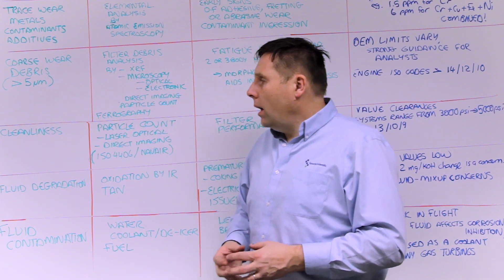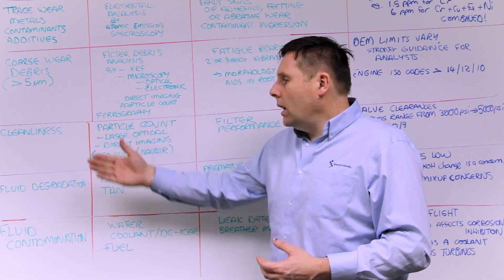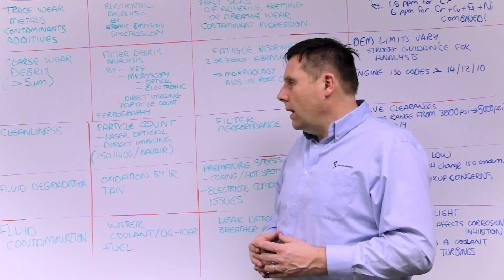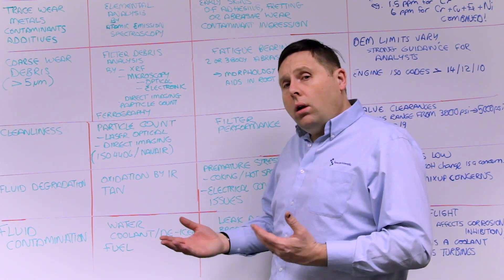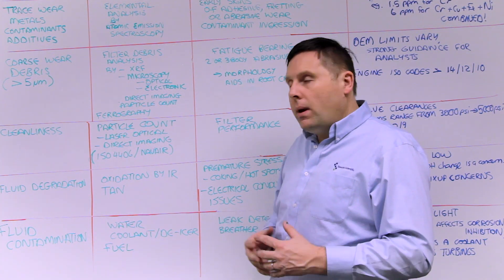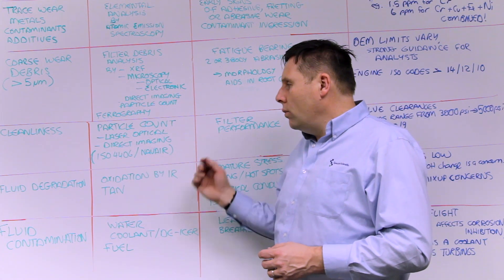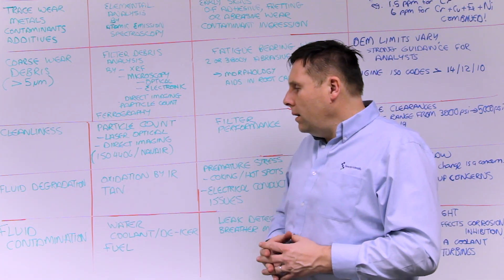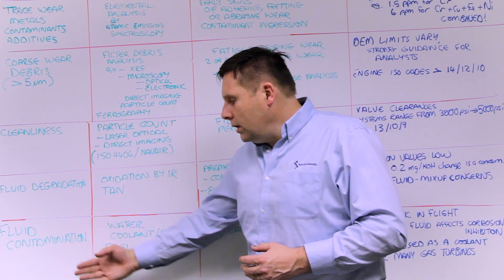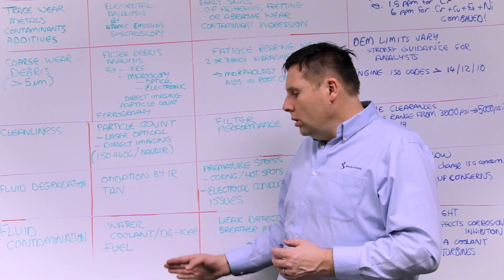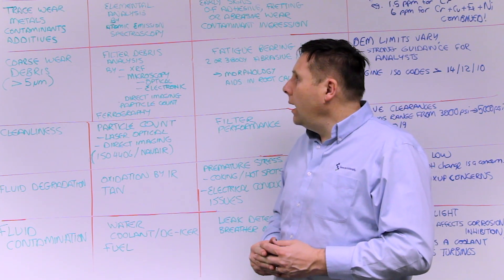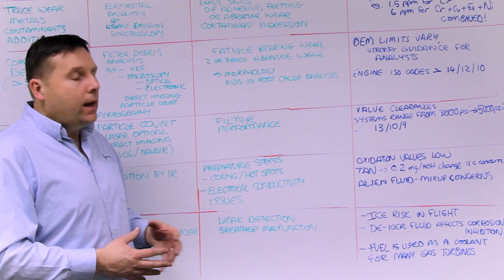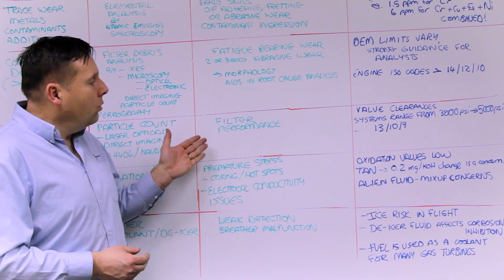Another level of properties we watch for is cleanliness, fluid degradation, and fluid contamination. For cleanliness, we look at overall particle counting and the general cleanliness level — particularly important for hydraulic systems and some engine applications — using ISO 4406 or NAS codes with laser or direct imaging. For fluid degradation, we look at oxidation by infrared and total acid number. For fluid contamination, we look for water, coolant, de-icer fluids, or fuel dilution issues.